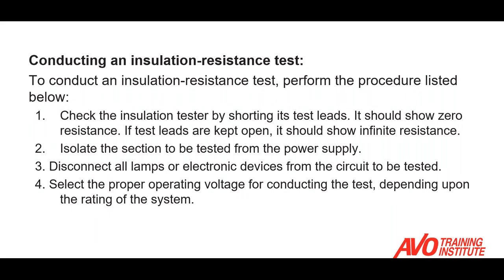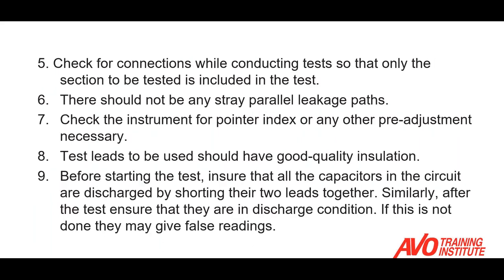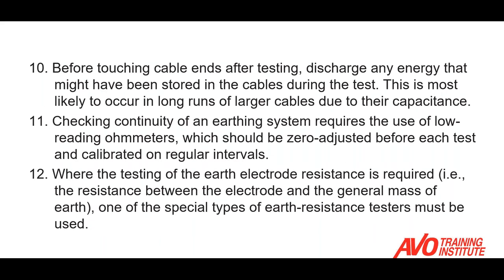To perform an insulation resistance test, first check the integrity of the leads by shorting the test leads — this should give zero resistance — and with leads kept open you should see infinite resistance. Isolate the section being tested from the power supply and ensure it's de-energized. Select the proper operating voltage on the insulation resistance tester depending on the rating of the system. Only the section to be tested is included in the test, and ensure that all capacitors in the circuit are discharged before starting. After the test, discharge any energy stored in the cables before touching the ends.